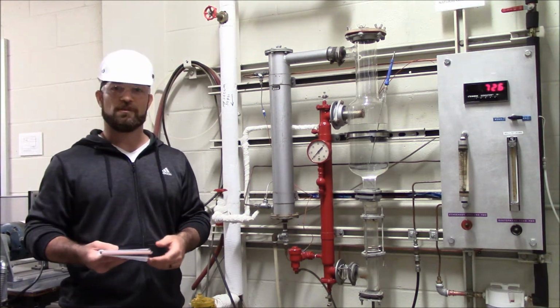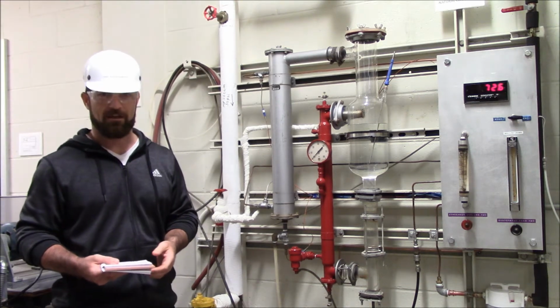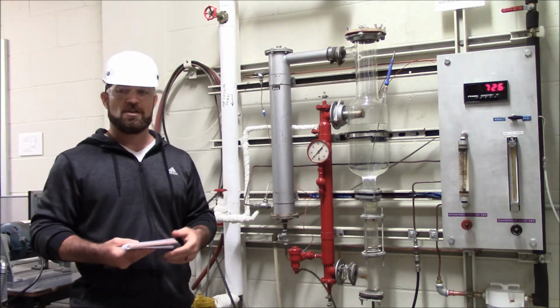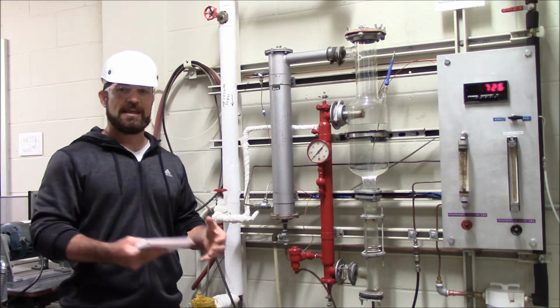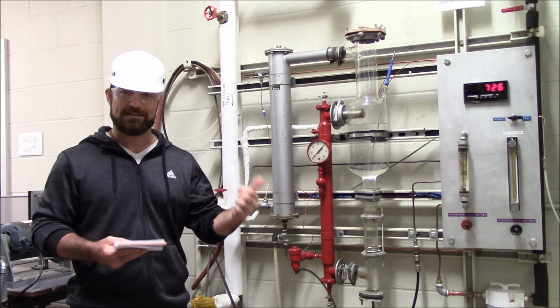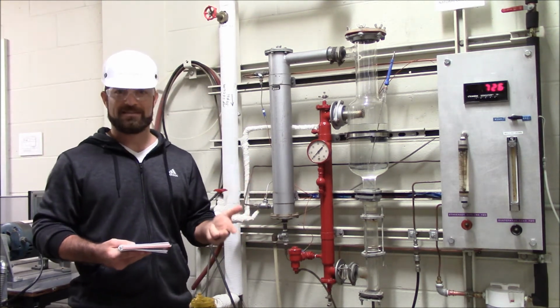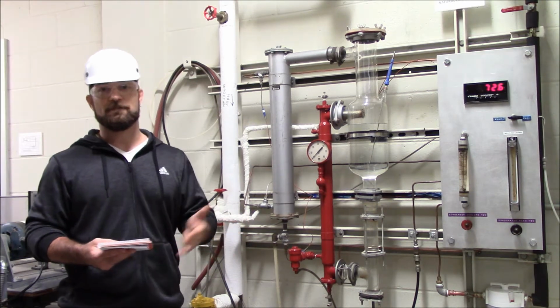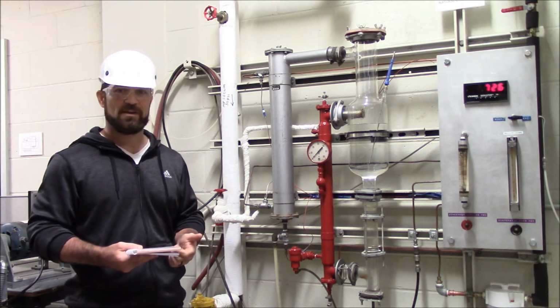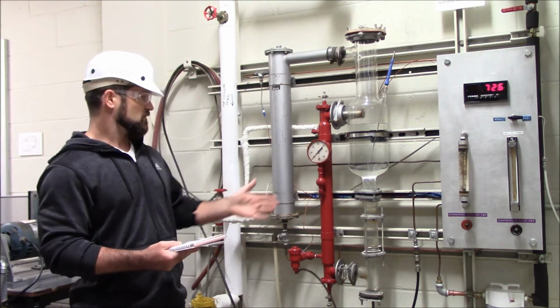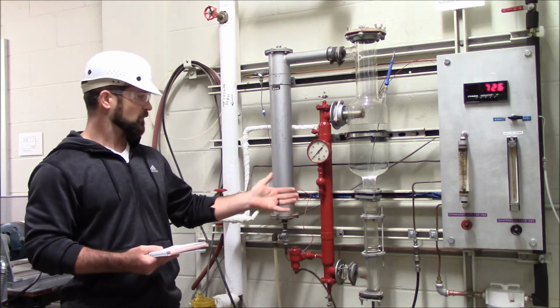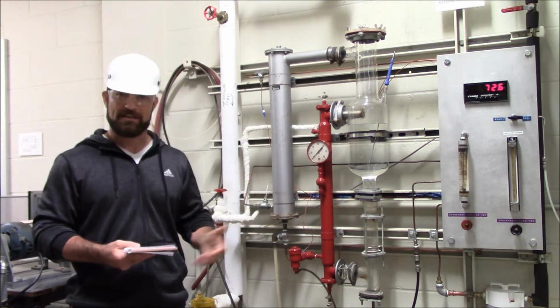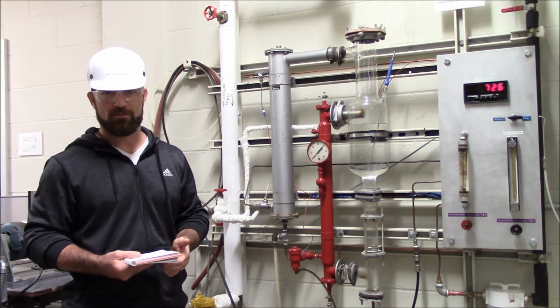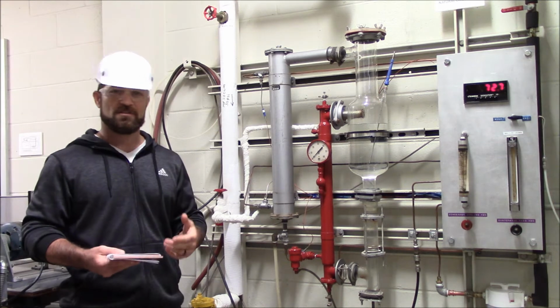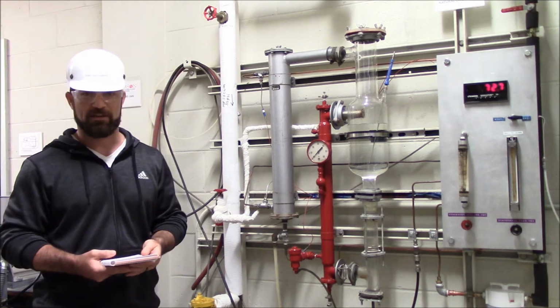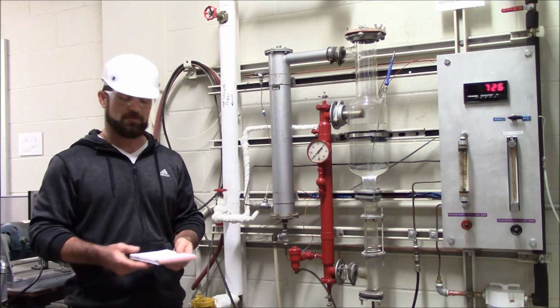Okay, sample calculations. Again, I'm going to refer you to the information provided in the course in terms of the sample calculations. But the general idea is you want to provide all the necessary calculations that take your measured values. The values you're going to measure are things like temperature, pressure, mass, and time. You want to take these measured values and convert them into useful information like Q, the rate of heat transferred from the evaporator, the rate of heat transferred from the steam, from the condenser cooling water, etc. And then how do you use these to calculate your heat transfer coefficient, U, for this experiment? Also, there's a design component, and you should provide some information on how to calculate the design objective for your experiment as well.